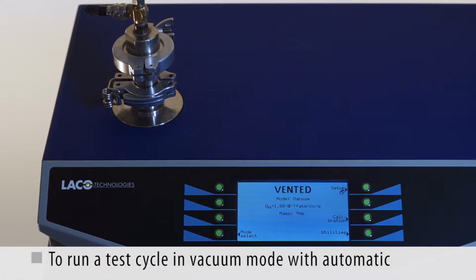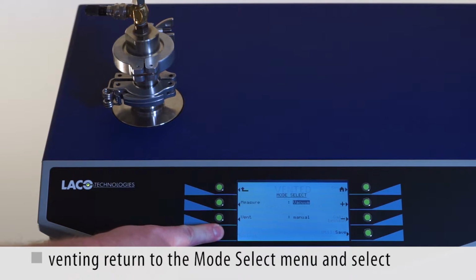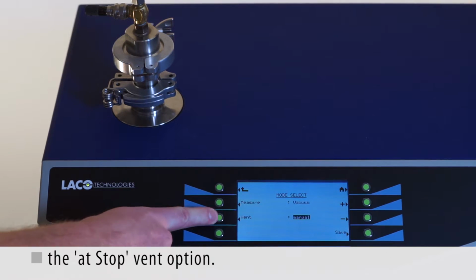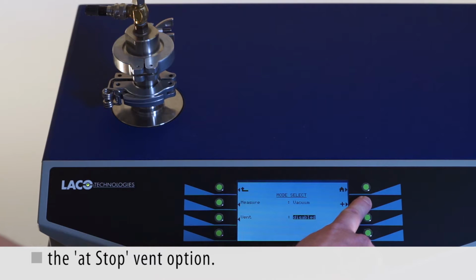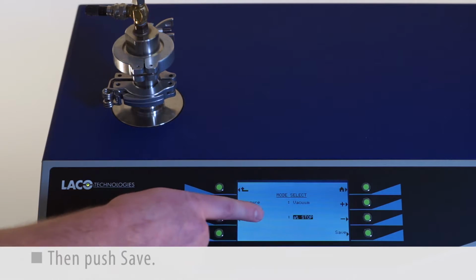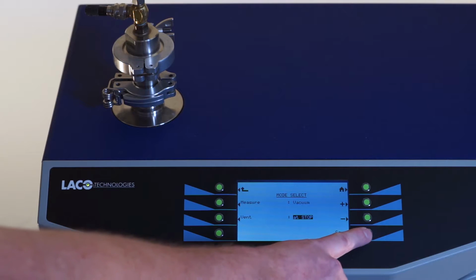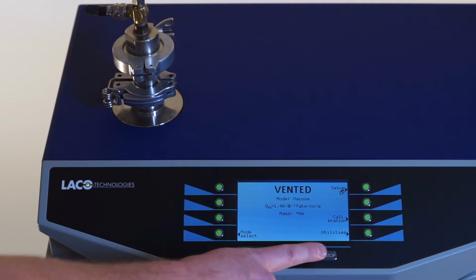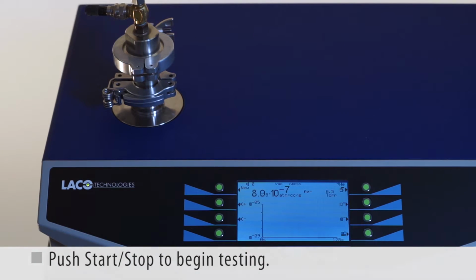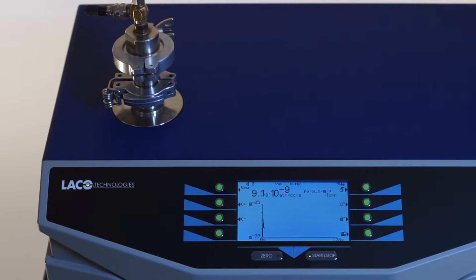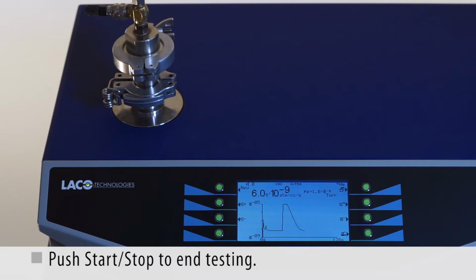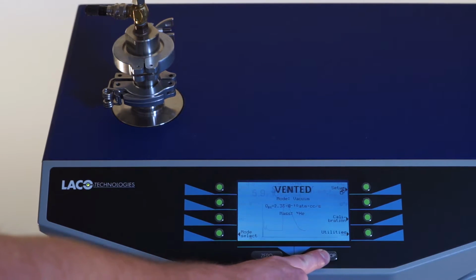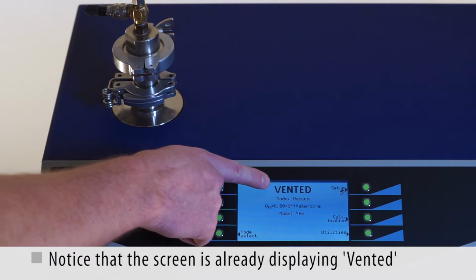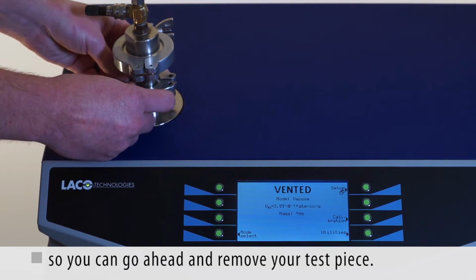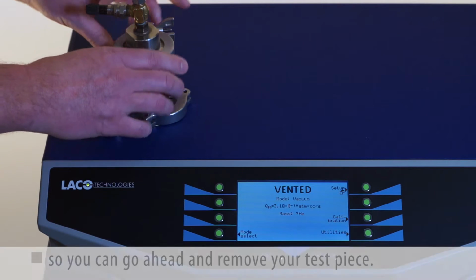To run a test cycle in vacuum mode with automatic venting, return to the Mode Select menu and select the At Stop Vent option. Then push Save. Push Start Stop to begin testing. Push Start Stop to end testing. Notice that the screen is already displaying vented, so you can go ahead and remove your test piece.